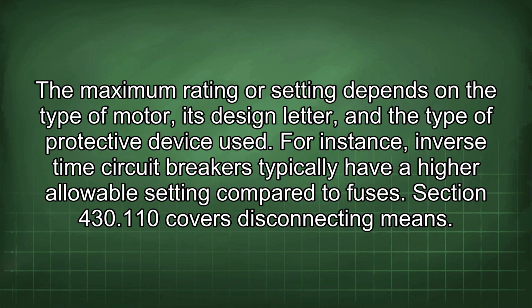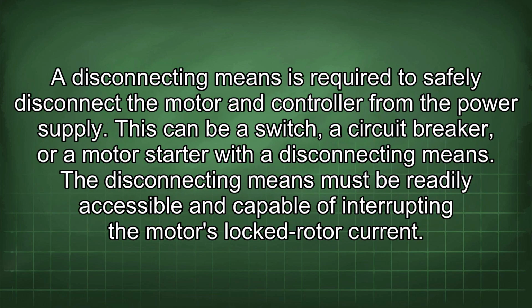Section 430.110 covers disconnecting means. A disconnecting means is required to safely disconnect the motor and controller from the power supply. This can be a switch, a circuit breaker, or a motor starter with a disconnecting means. The disconnecting means must be readily accessible and capable of interrupting the motor's locked rotor current.